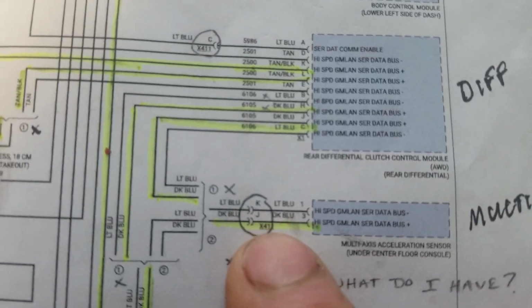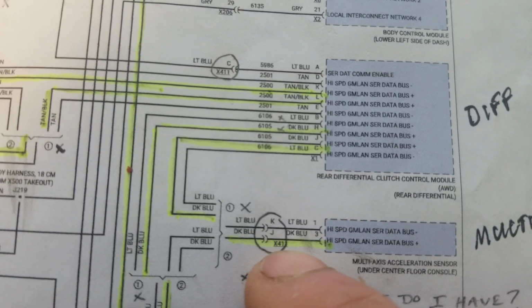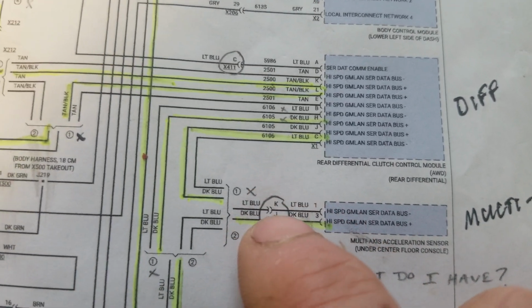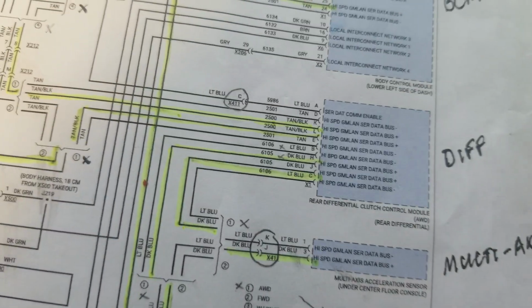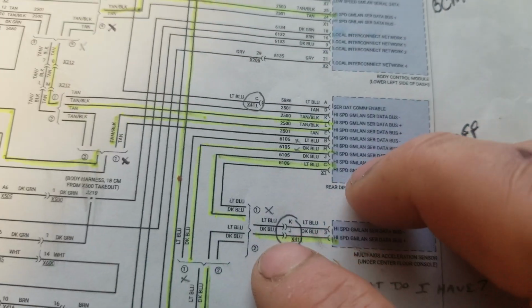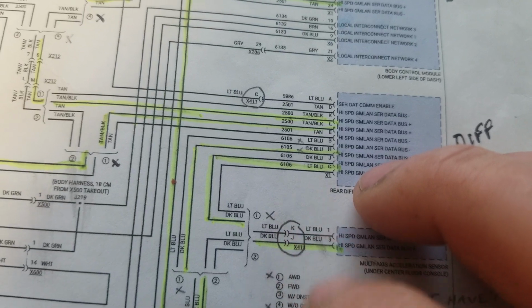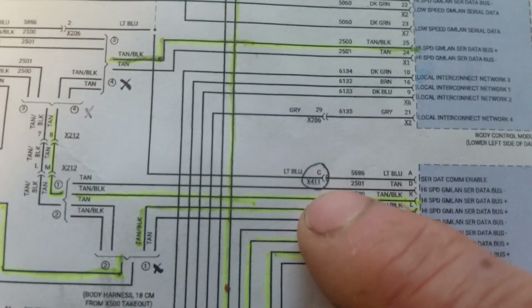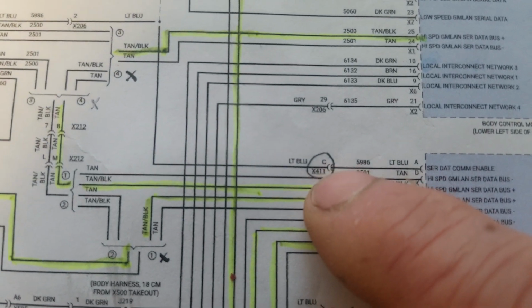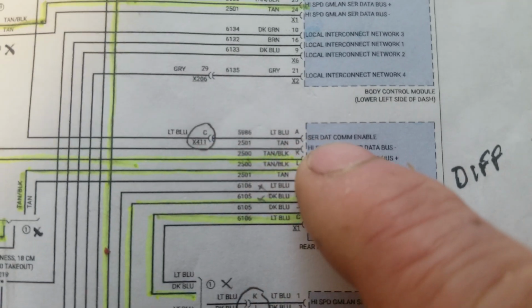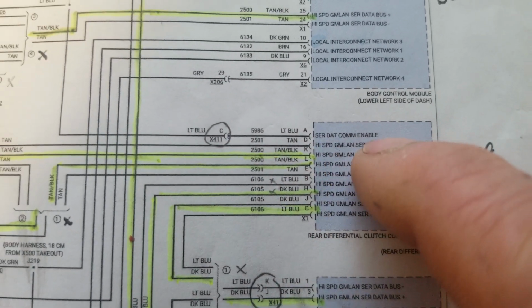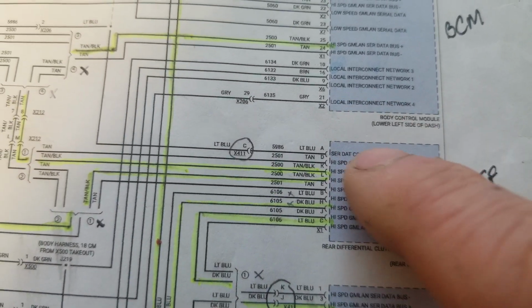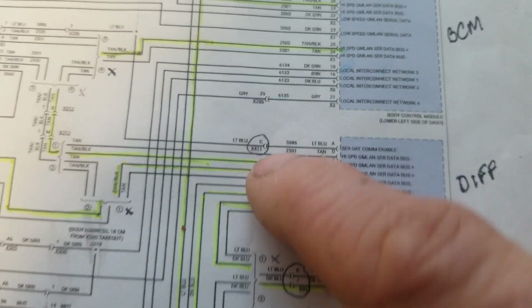Oh, so it's important to remember on the connector X411 that J and K basically means that those are the pins labeled for these wires, okay? So there are multiple wires going to X411, and if I look at my diagram, I found X411 here labeled C. So where that wire there says serial data comm enable. Now I want to talk about serial data comm enable, and I will here in a second, but let's find the rest of X411.